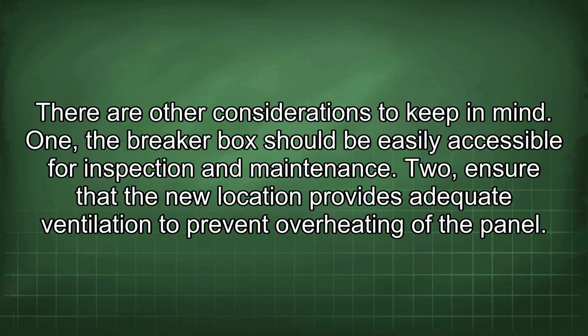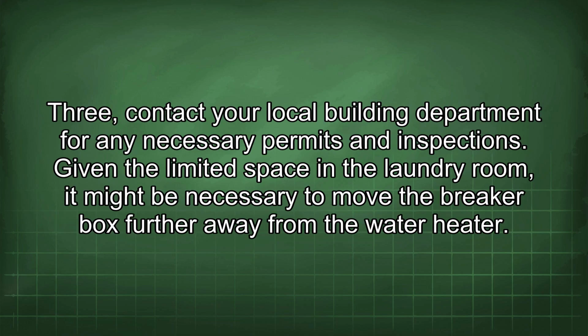There are other considerations to keep in mind. 1. The breaker box should be easily accessible for inspection and maintenance. 2. Ensure that the new location provides adequate ventilation to prevent overheating of the panel. 3. Contact your local building department for any necessary permits and inspections.